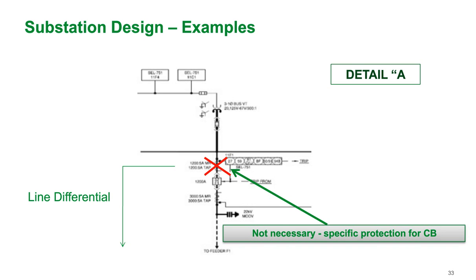At 38 kV, typically the size change between GIS and air insulated switchgear, or between a large transformer, is very different. So close coupling can be done just with an adjoining piece of sheet metal, but there's not a direct bus bar connection typically with GIS to other switchgear or transformer.